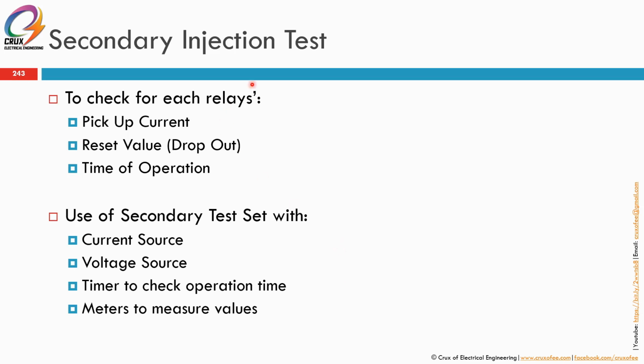Then we have the secondary injection test to check for each relay pickup current, reset value, dropout. This is for all types of electromechanical relay. For new type relays, you can enable this within the relay, but normally the reset value or dropout time is instantaneous. And then also to check for the time of operation, whether it's for instantaneous or the IDMT and so on. Instantaneous is not really instantaneous. There's at most 40 to 50 milliseconds delay. For IDMT, you have to refer back to the curve.